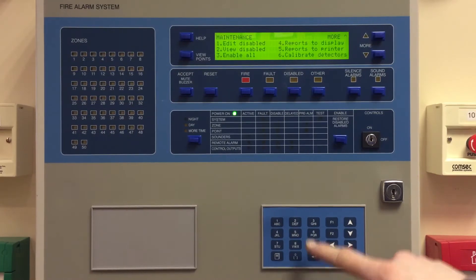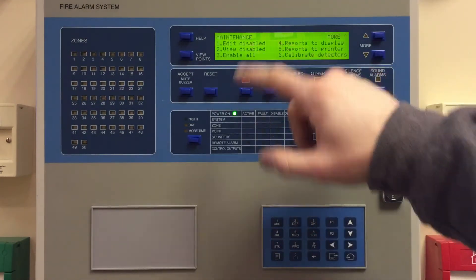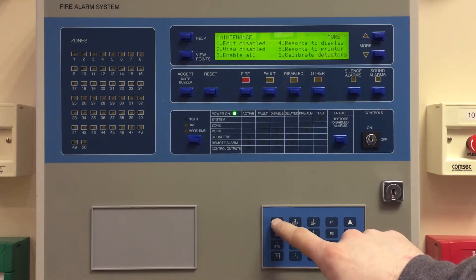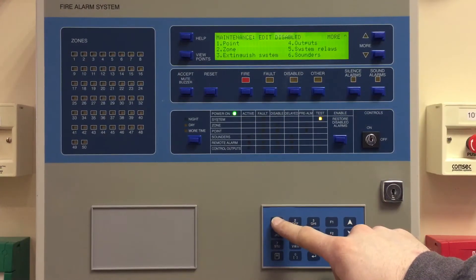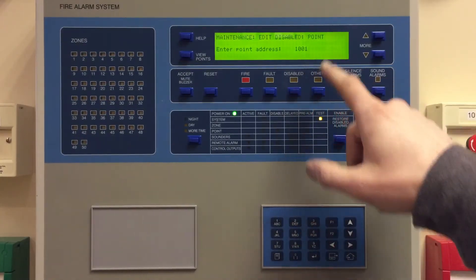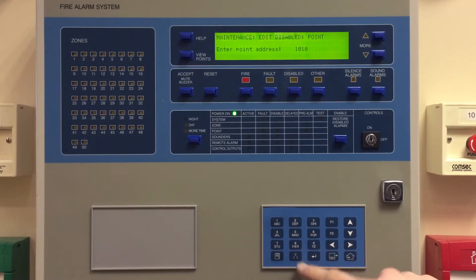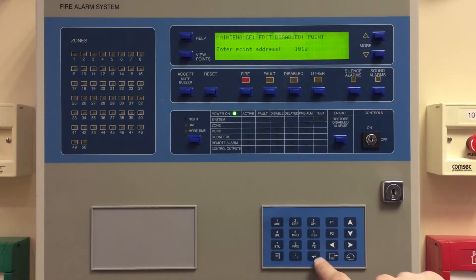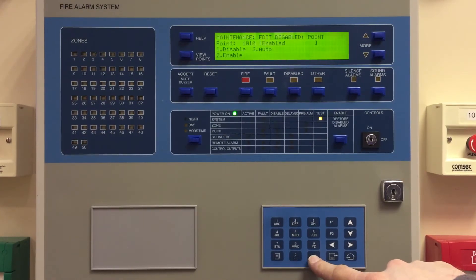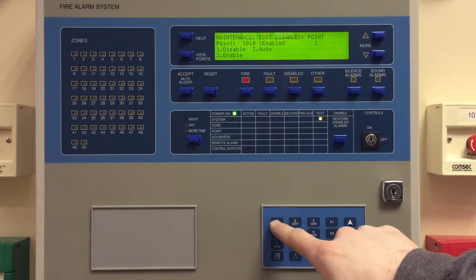When you come in here you see a selection of menus. The one we're looking for is Edit Disabled. Today we want to do a point, so it's one for point, then you enter the point address — so we go 1010. If your panel is networked you'll see an option to add in the panel address as well, so you can disable equipment across the network. We're just interested in this point for now, and currently it's enabled, so we want to do one for Disable.